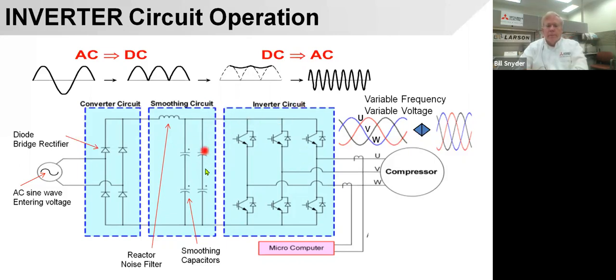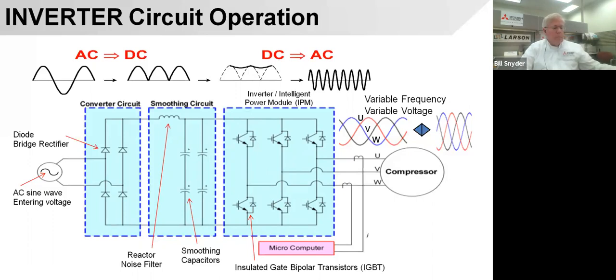Then we go into this inverter circuit. So we take 300 volts into this inverter circuit, and we go through these, they call them insulated gate bipolar transistors, or IGBTs. They're gates, like a triac, if you're familiar with those. And there's a set here, here, and here. There's 3 sets of these, or 6 of them in there. And we're taking this DC voltage and we're running it through these. And what we're doing is we are simulating AC voltage when we come out of it. It's called a sinusoidal 3-phase pulse width modulation, or pulse amplitude modulation, that we put out of here. So we're putting out 3 simulated AC signals out of here. And they go to the compressor, and they're labeled U, V, and W.